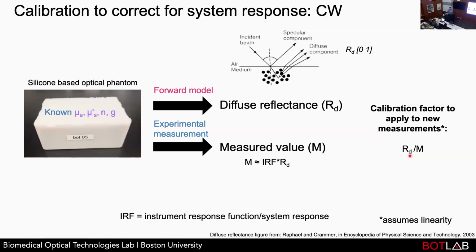I was just at Modulim yesterday. They have determined that the device is pretty stable over time, so you don't need to take a calibration measurement as often. Maybe you do it once a month or once a year. I'm not saying that's what they do for their device, but it's less often like that. It depends, and you have to test to make sure that it's stable.